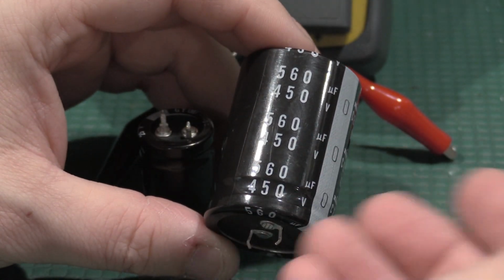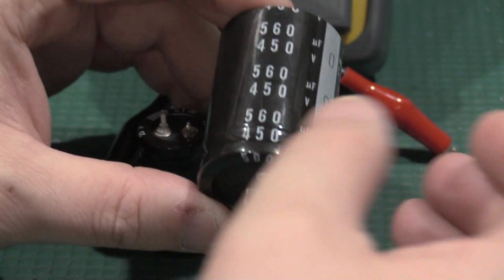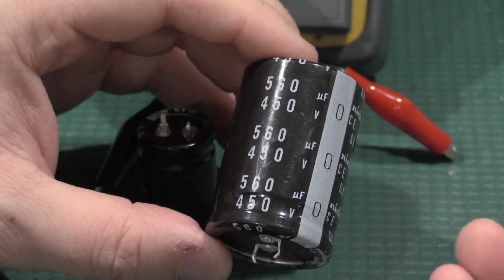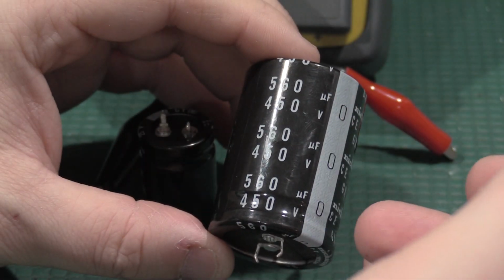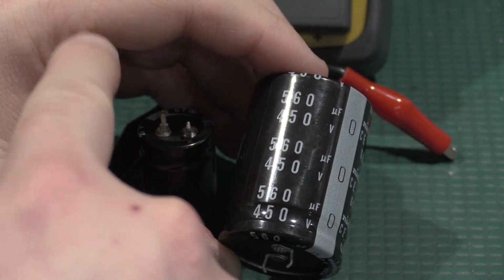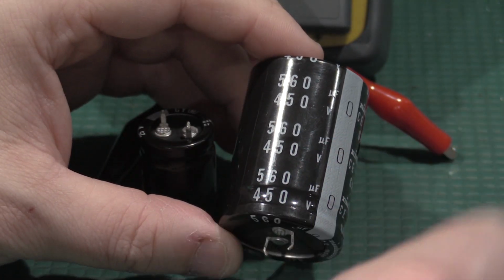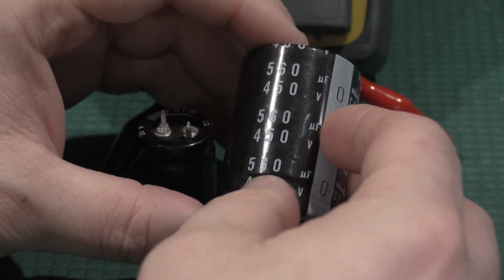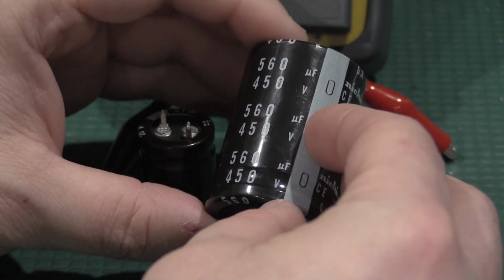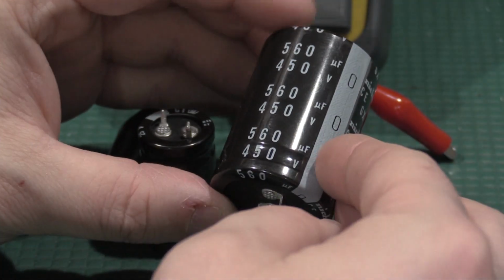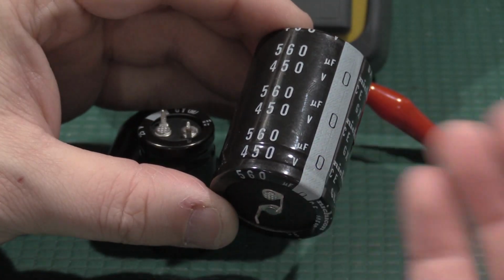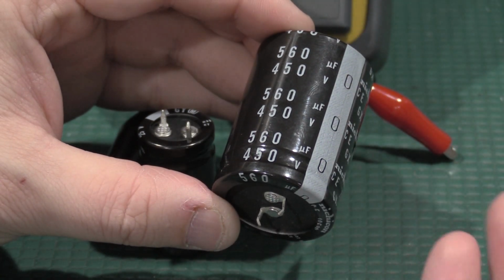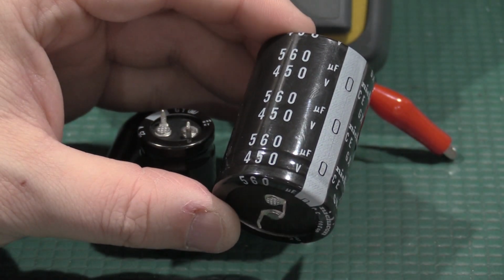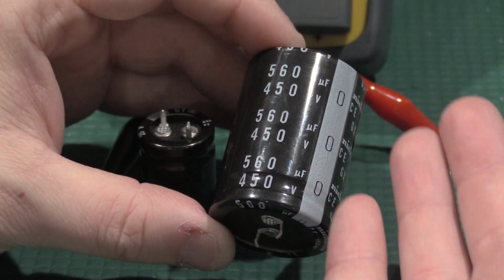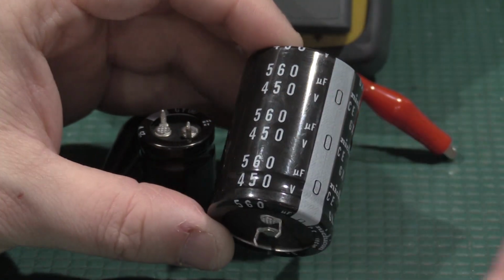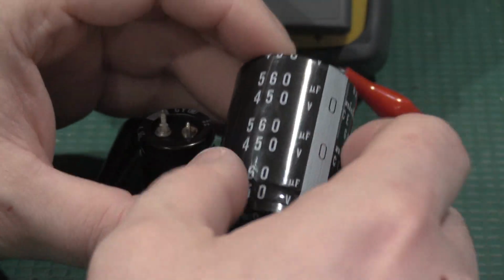Now, there is still a reformation period, even with modern capacitors, which I can actually show on some of my equipment. If you look at the leakage current through the capacitor, it'll peak and then come down and then level off at a value. And actually, in the data sheets, to get the leakage value, there's a procedure where they say you have to bring the cap up to the working voltage. It has to be there for so long, and then you can do a leakage test to make sure it's in specification. Even the manufacturers are counting on a mild reformation process to bring the capacitor back into spec.